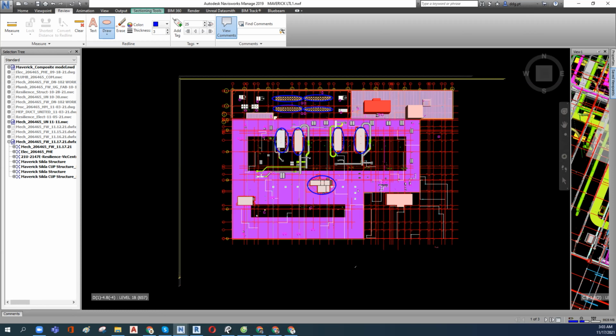The reason why this becomes a little more complex is because lineal footage wise, you're restricted by the overall length of footage you can run on a circuit. Because of that, what you typically do is say I'm covering the chill water pipe — I'll start at the bottom and run up and cover the chill water pipe, then continuously put a jumper that goes from the chill water supply to the chill water return. Then I'll go down the chill water pipe, so you're trying to keep a continuous circuit. Sometimes you've got to put a junction box in there and splice into the next section, but basically that would be one circuit that would feed that entire rooftop unit.